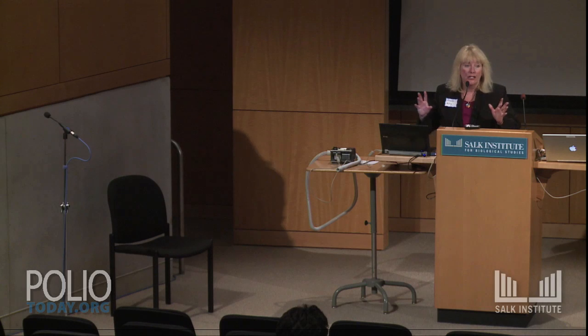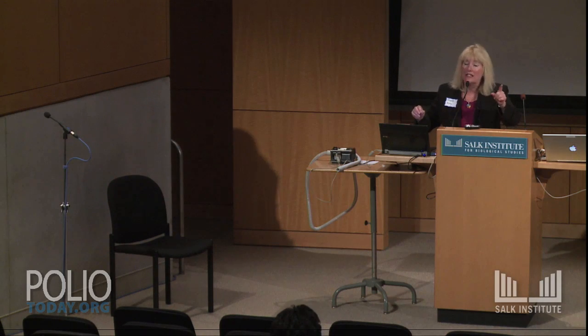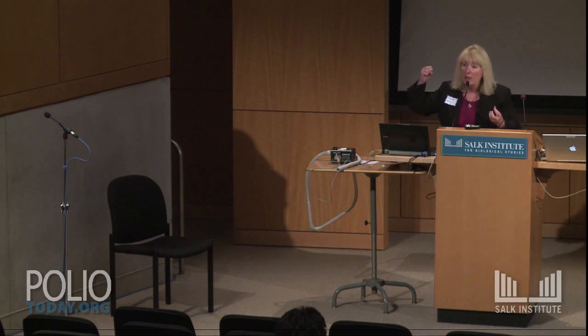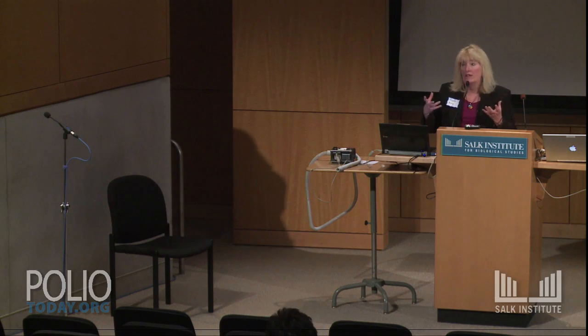Well, the first thing I would check is, are you having undue leak? Because if you're having a big leak, what does the machine do when it sees a leak? It compensates, exactly right, that's a good thing. But how does it compensate? By sending a lot of extra flow. So sometimes that extra flow can be very drying.